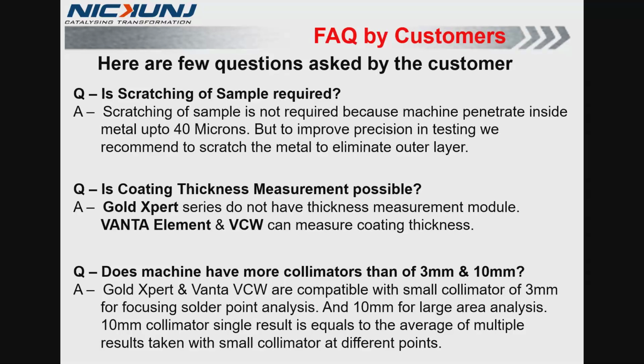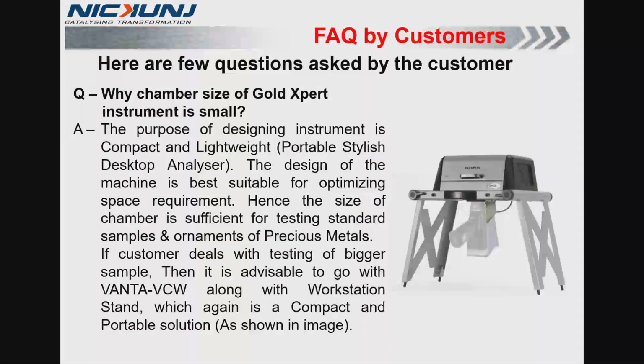Does machine have more collimators than 3 mm and 10 mm? Gold Xpert and Vanta VCW are compatible with small collimator of 3 mm for focusing solder point analysis and 10 mm for large area analysis. A 10 mm collimator single result is equal to the average of multiple results taken with the small collimator at different points.